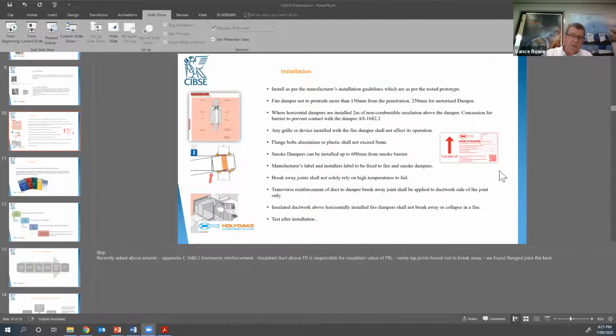And if those two systems both fail, if you look inside the fire damper, you'll see the manufacturer's label on there. And all of us manufacturers are required to put those labels on the dampers. So it's inside a fire damper. So if the damper's in the duct, obviously you need an access panel to see that. Yeah. So that's not always visible. If it's a 200 by 200 duct, you're not going to be able to get your head in. So you're going to have to use a miniature camera or something.